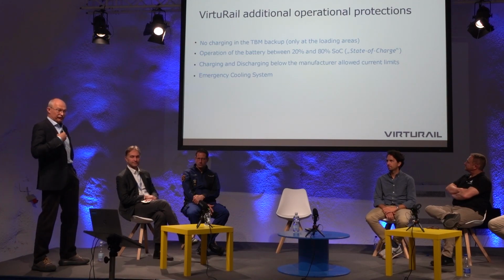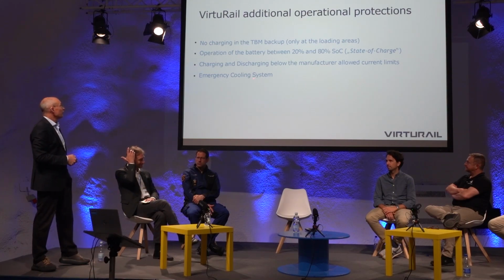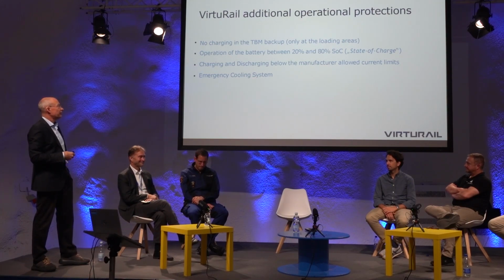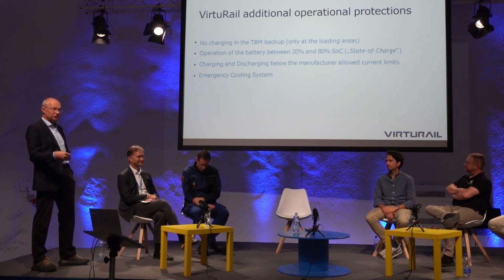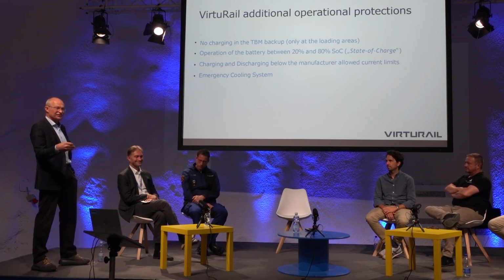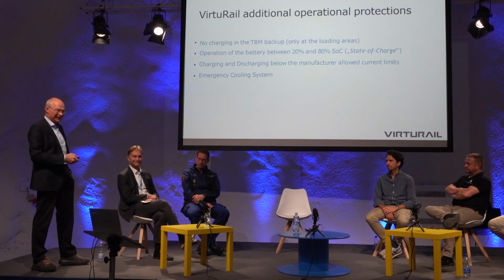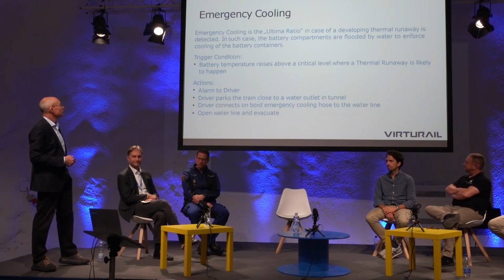So we have to have capacity to go in and out and charge outside in the loading area. We operate the battery only between 20 and 80% state of charge. This is the safe area, and also the best lifetime area of the battery. We charge and discharge below the manufacturer allowed current limits, and we have the emergency cooling system, which is the ultima ratio.